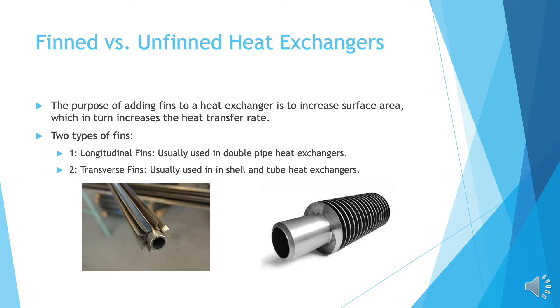This brings me to finned versus unfinned heat exchangers. Adding fins to heat exchangers is important because it increases the surface area of the exchanger, which in turn increases the heat transfer rate. This will not always be necessary, but if you have a low heat transfer coefficient on the outside of the tubes, it might be worth considering adding fins to improve efficacy. There are two types of fins: longitudinal and transverse fins, each with their own expertise. Longitudinal fins are better for when you want the flow outside of the tube to run along the entire length of the tube, like double pipe heat exchangers. Transverse fins are more often used for shell and tube heat exchangers or turbulent fluids because they can restrict movement.